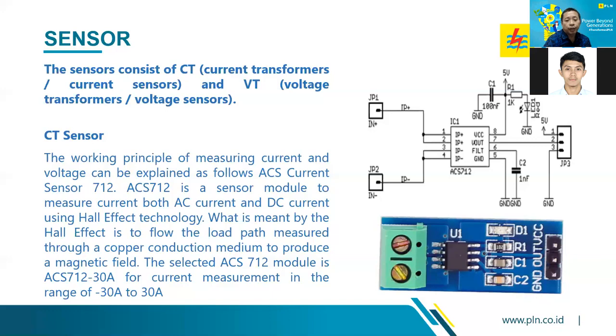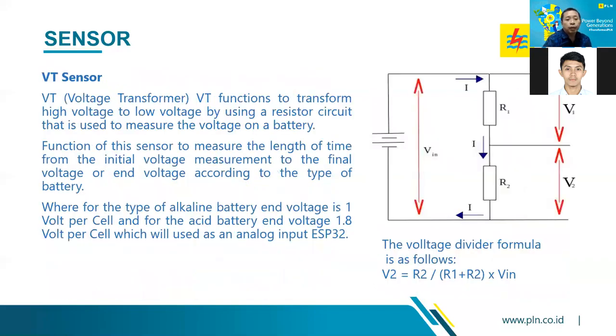The selected module is ACS712 minus 30 ampere, for current measurement in the range of minus 30 ampere to 30 ampere. And besides the electronic circuit, after the CT sensor comes the VT sensor, or voltage transformer. Its function is to transfer high voltage to low voltage by using a resistor circuit that is used to measure the voltage on a battery.